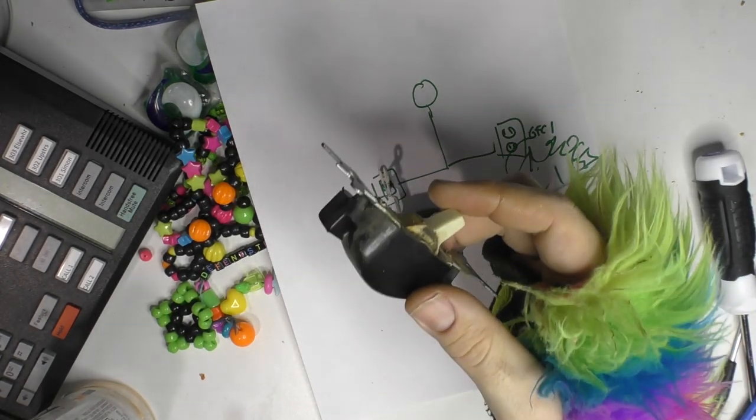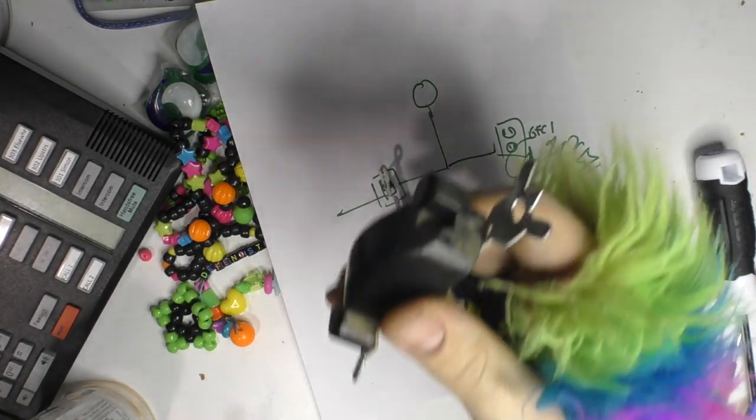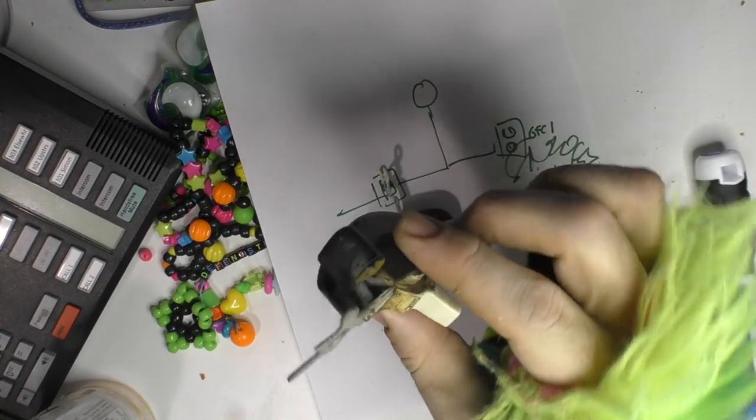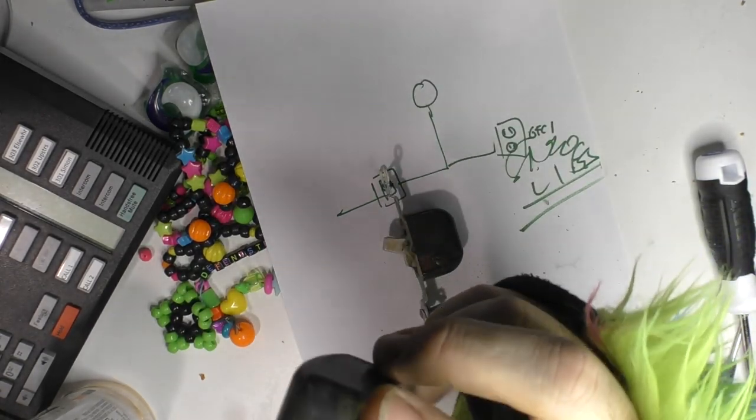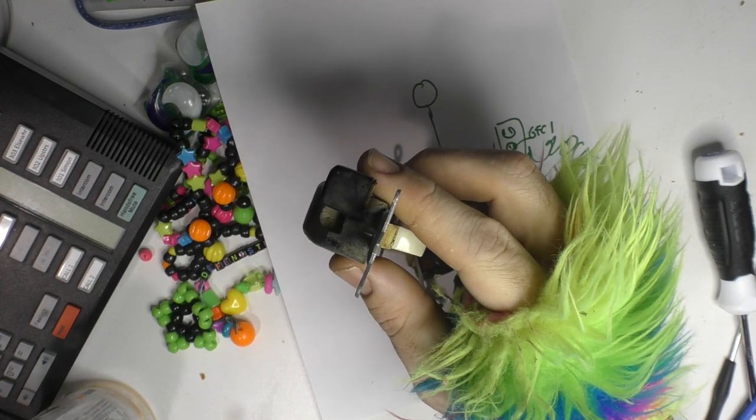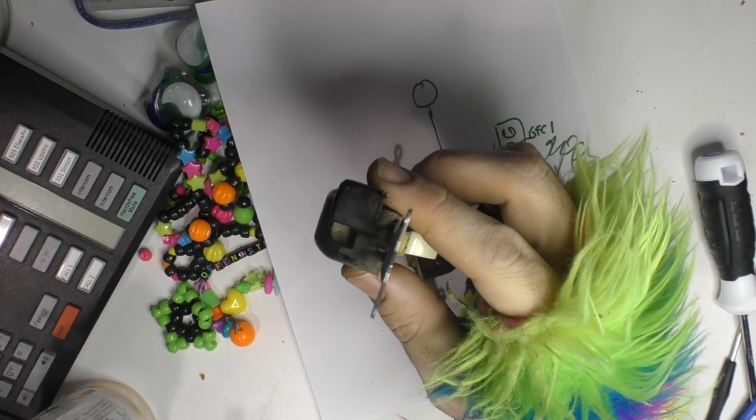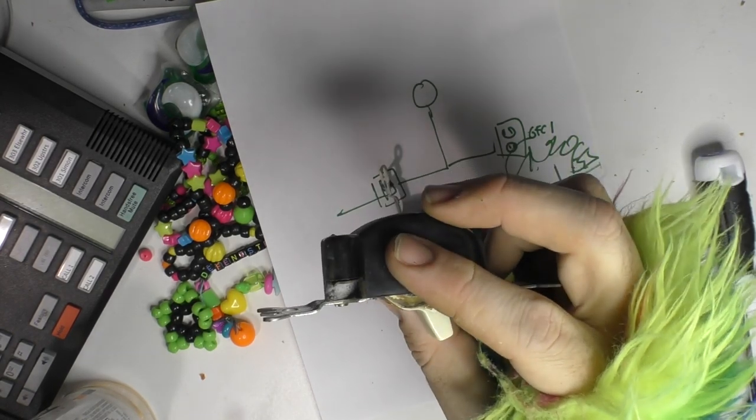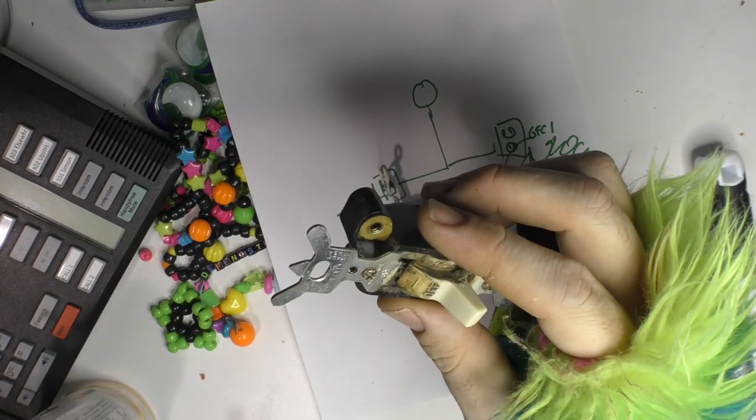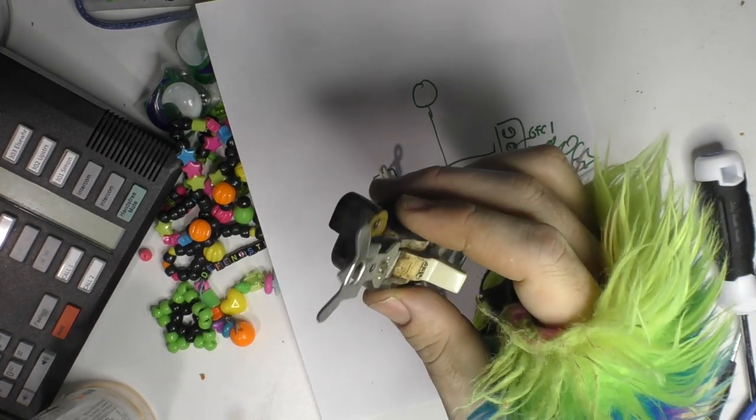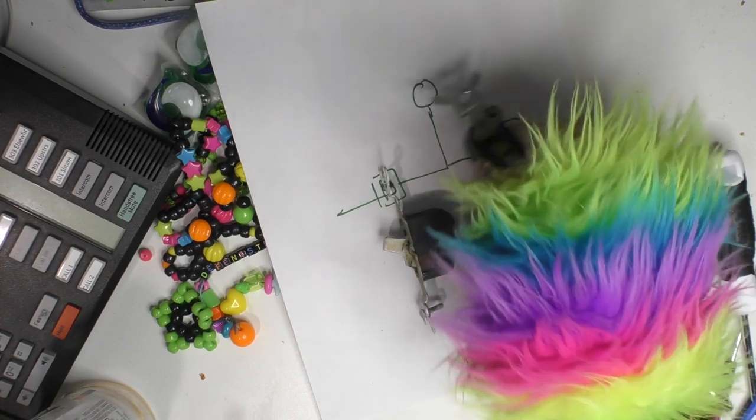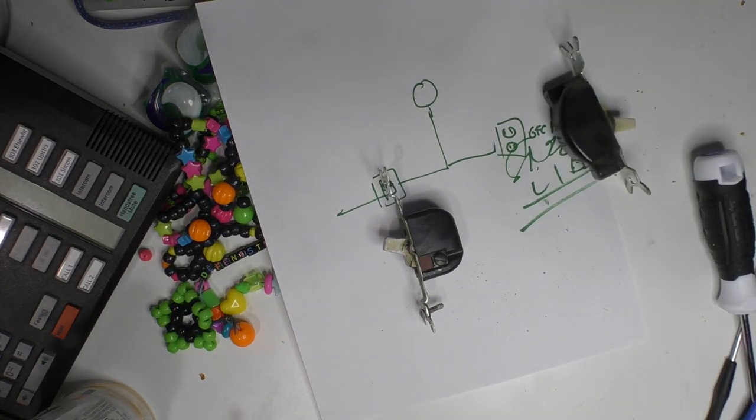So even though this is a very old ass fucking switch and it does not have a grounding screw or a grounding connection, this metal plate is connected to the metal box which is grounded in this house, as it should be. So it is possible that a short developed in the switch and that's what blew the circuit. But either way, I want to find out because if my wife's going to be using this hair dryer, I want to know what's going on.